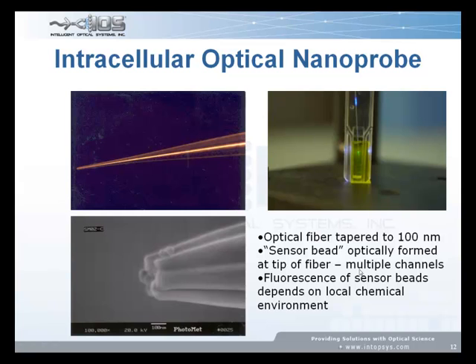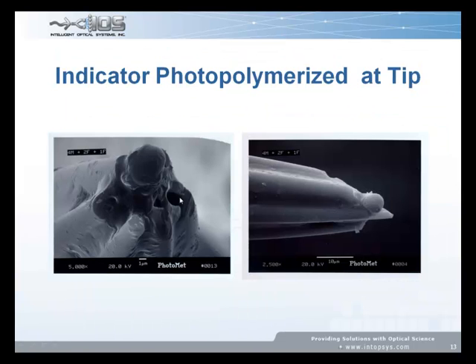But what we do is we take this tip, shine light into one of the optical channels, and dip it into a monomer solution that has a UV curable polymer in it, and an optical indicator dye. So in the end, what you wind up with is a little bead, a little dot, exactly in the near optical field of light that's squirting out of that little tiny sub-wavelength hole. And here's even a better picture of it.